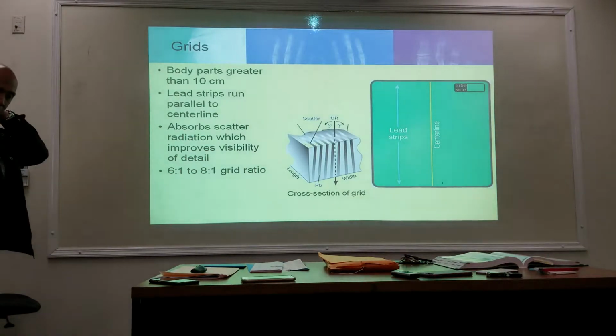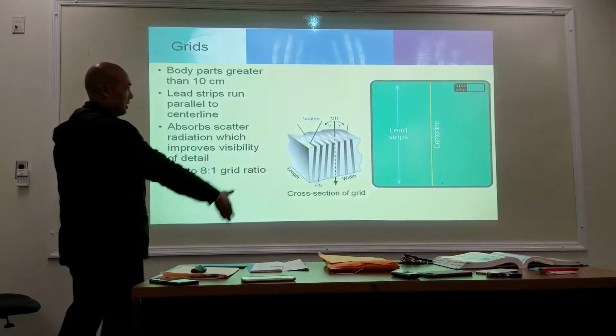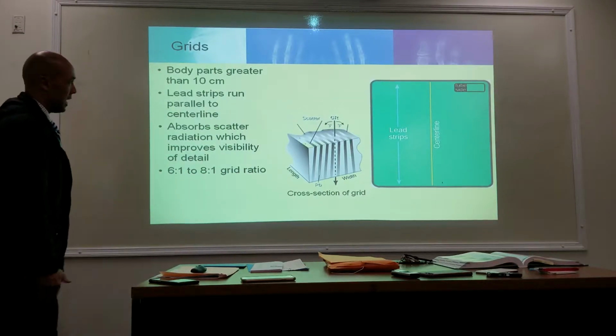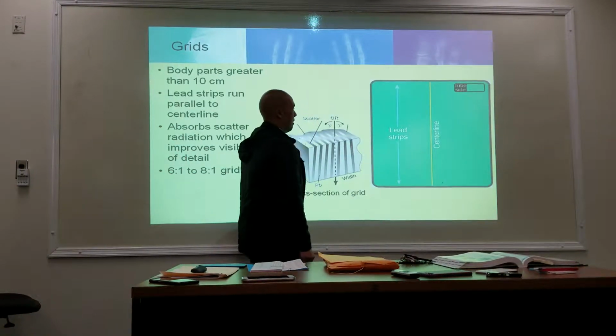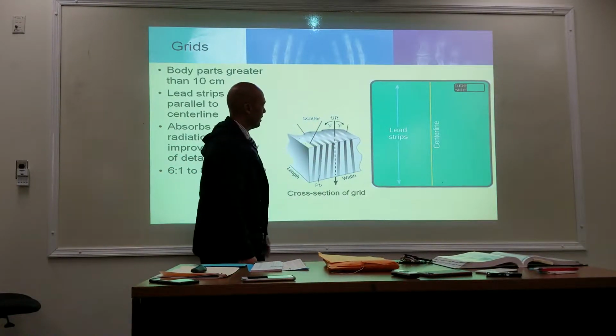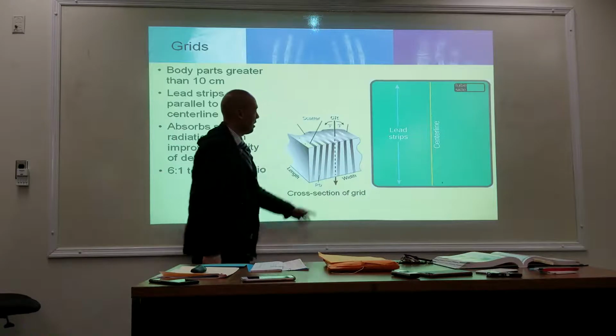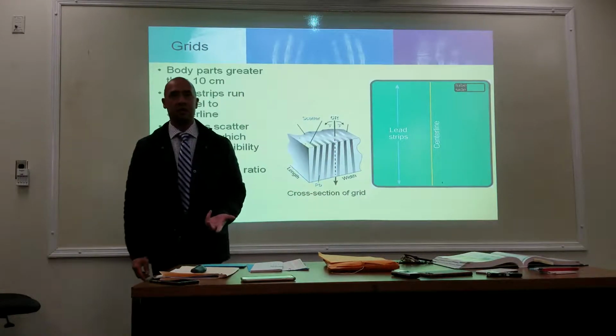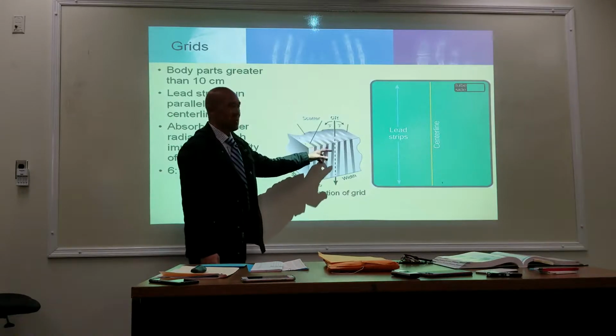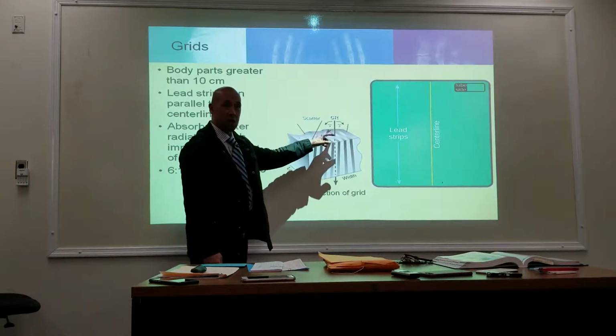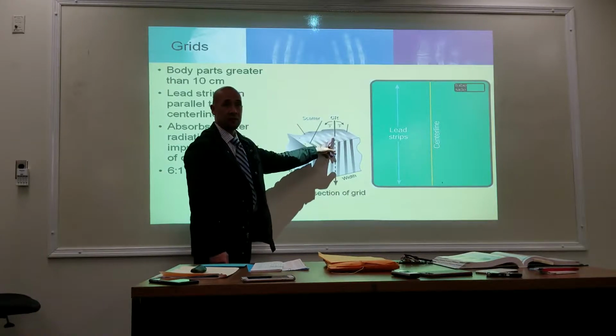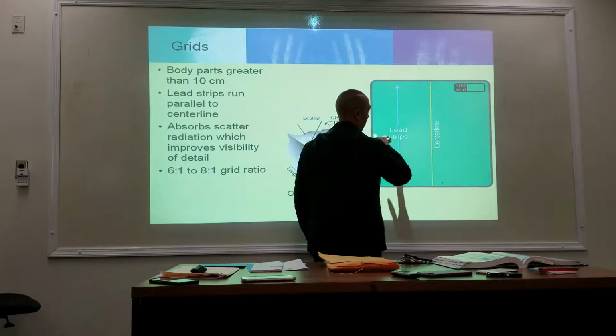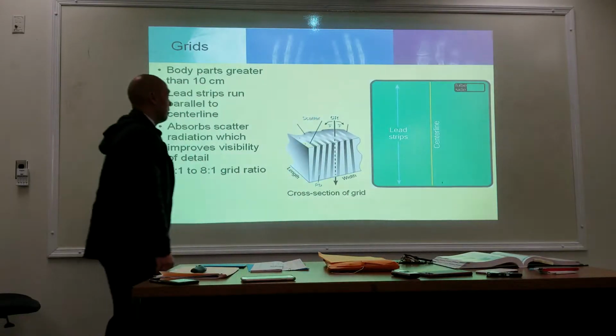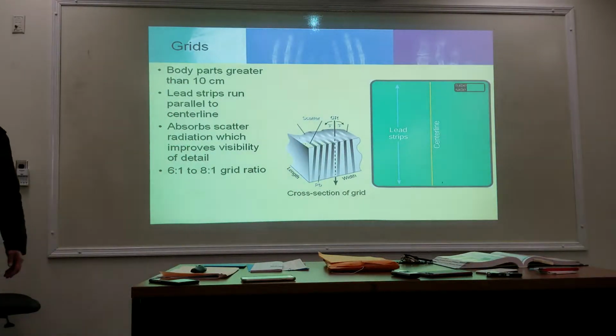So this basically covers what we just talked about. The lead strips run the length of the grid. You can angle this way, but I can't angle this way. Okay, here's your forgiveness. If I'm not perfectly straight, I can have a slight angle either way, as long as it's within, it says here, an example of 3-degree angulation. You get a larger margin of error with lower grid ratios. With higher grid ratios, you may not have that angulation or that forgiveness coming in this way. Okay?